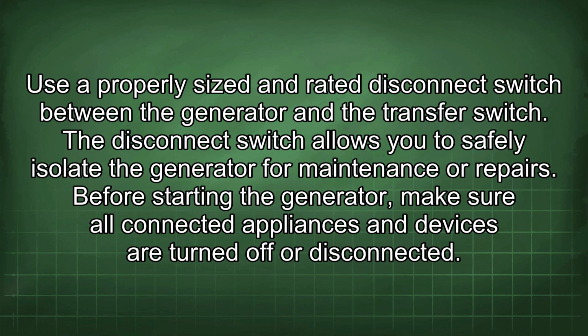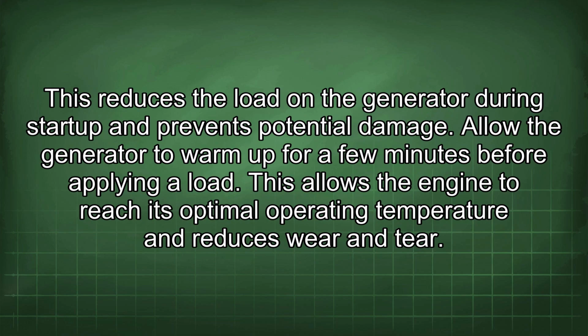The disconnect switch allows you to safely isolate the generator for maintenance or repairs. Before starting the generator, make sure all connected appliances and devices are turned off or disconnected. This reduces the load on the generator during startup and prevents potential damage. Allow the generator to warm up for a few minutes before applying a load. This allows the engine to reach its optimal operating temperature and reduces wear and tear.